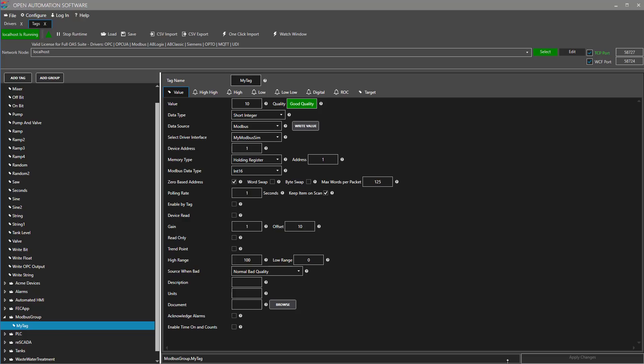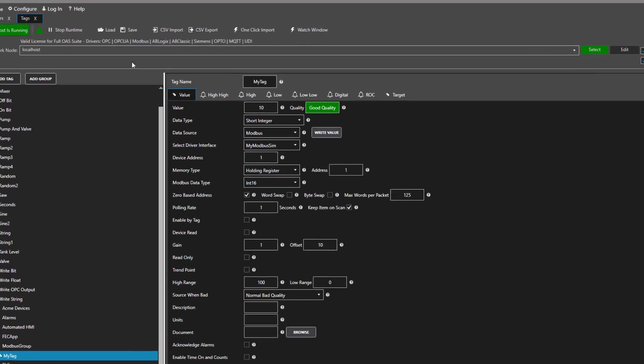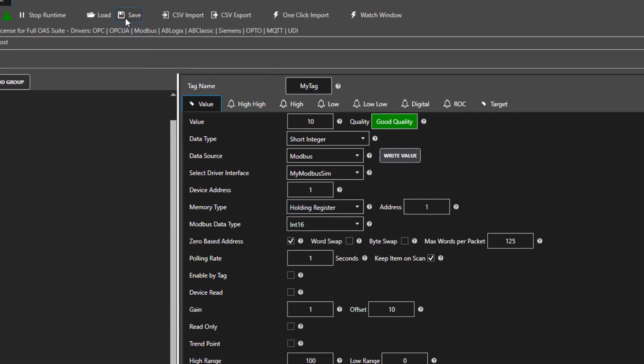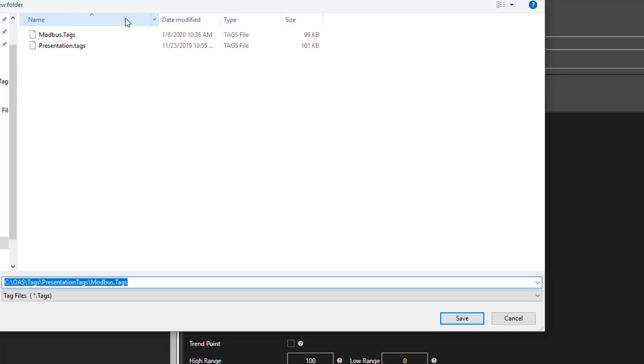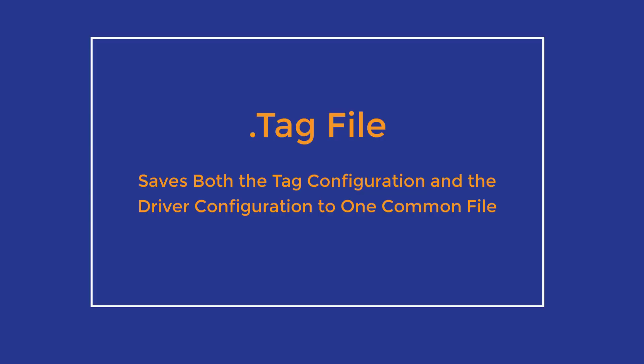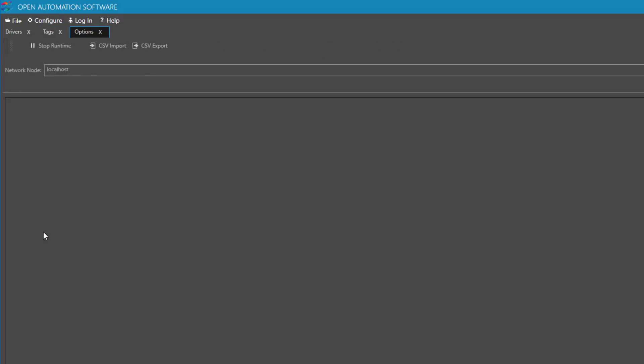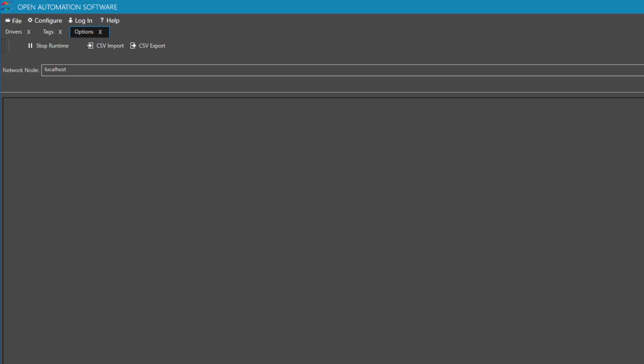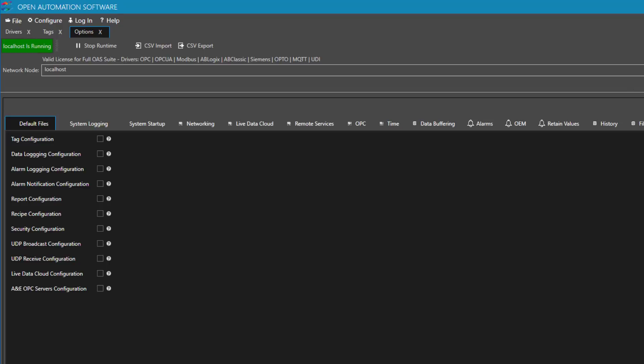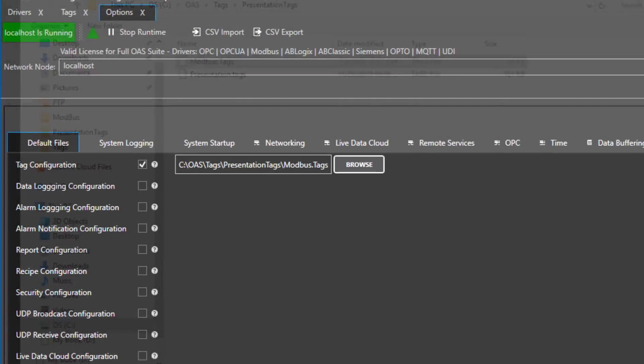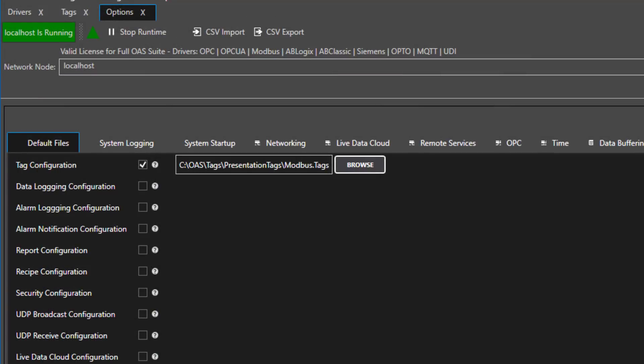One of the final steps is to save your tag configuration. When you save your tag file, it saves both the driver interface configuration that you have created, as well as the tag configuration. They will both be saved in this common file. Then, if you go to Configure Options and select the local service, you can specify the default tag configuration to load when the system restarts. This is important so that the service will run unattended if your operating system restarts.